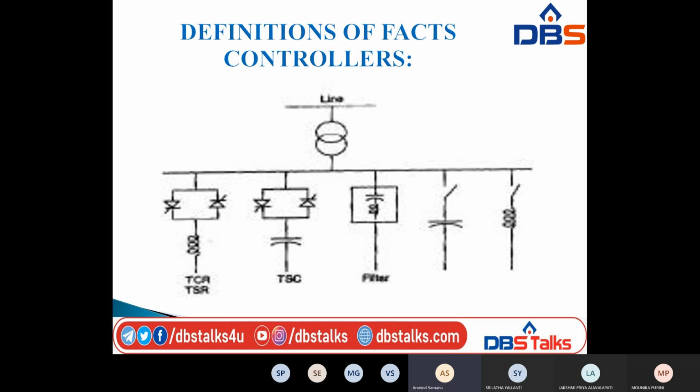Here the effective reactance is varied in a stepwise manner by full or zero conduction operation of the thyristor valve. So this TSC is also a subset of SVC, in which thyristor based AC switches are used to switch in and out shunt capacitor units.